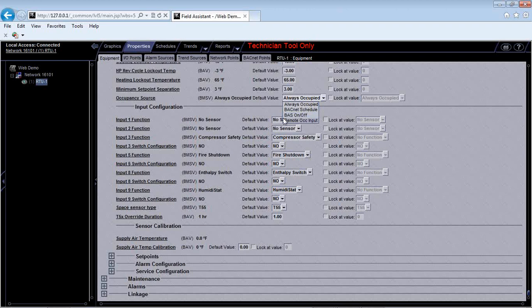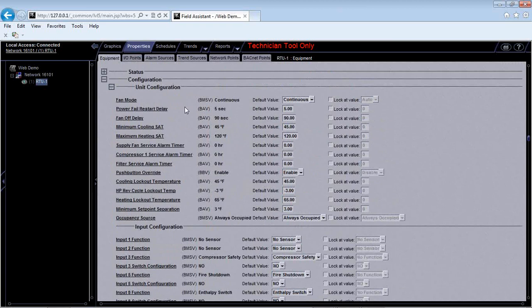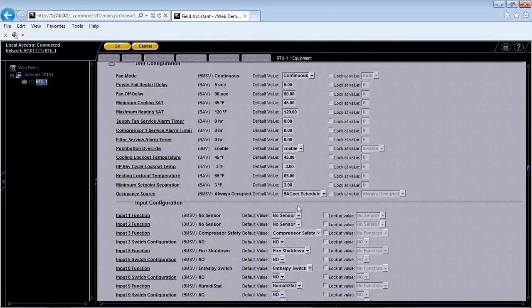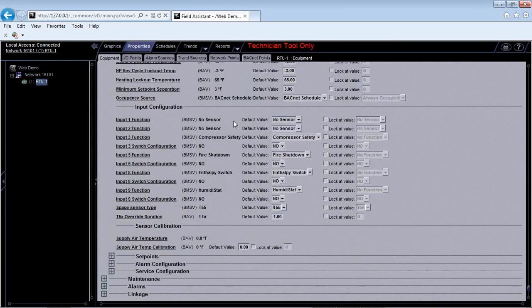And then the final one is remote occupancy input. This is basically the same as the BAS on-off, except it's actually a hardwired point. This is a closing contact that you hardwire into the rooftop controller, the RTU open controller, and when it reads closed, the unit goes into occupied mode. Some people like hardwire versus the network. Doesn't really matter to me. Both of them are going to turn it on. So that's the first part of unit configuration, setting up your limits and how you want the unit to run. I'm actually going to set this up as Bacnet Schedule here. Hit OK.